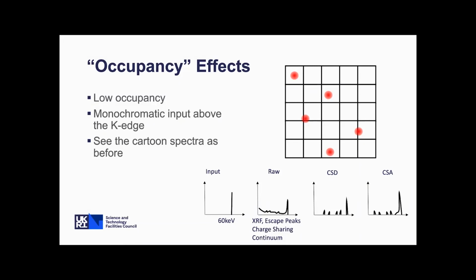I mentioned before the charge sharing. When we've got our little array of pixels here with X-ray events across them, at low occupancy, if we have a monochromatic input, then we'll get a nice single peak as an input. The spectrum that we'll see from raw data is this continuum from charge sharing, some X-ray fluorescence peaks, and then the peak at the correct energy. When we do the charge sharing discrimination, we get no continuum, we get the nice peaks. And when we do the charge sharing addition, we get the full peak height recovered, with some slight broadening because of the charge lost.